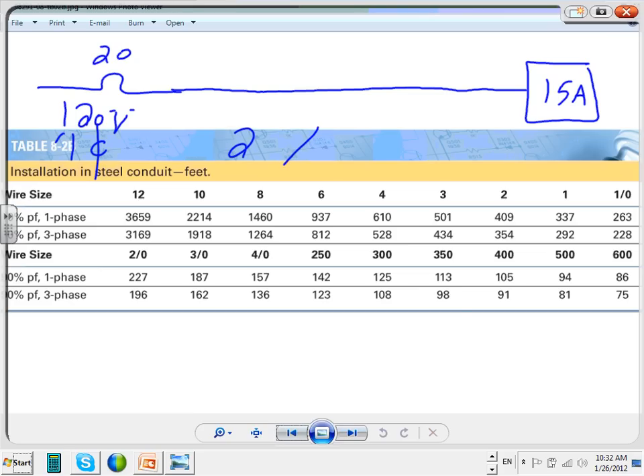So for 2% voltage drop, how far can I put this load away from the panel? One more time. It's a 20 amp circuit breaker, and I have 120 single phase. I need to maintain 2% voltage drop. How far can I put this conductor, this load away from the panel based on this table? You can do the math, but based on this table, oh yeah, I need a conductor. Let's just say the conductor is number 12. Okay, how far? So we have a 15 amp load, number 12, single phase. What did you guys come up with? 47 feet. Anybody come up with something different? 47 feet. We're looking at the voltage 120, the bottom side of the voltage. So they can't be more than 47 feet away from each other.